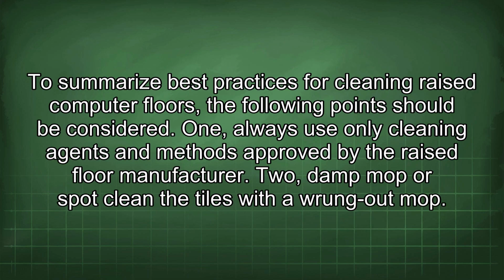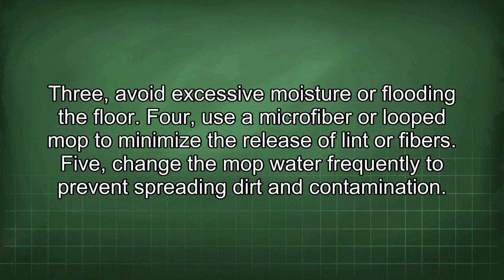To summarize best practices for cleaning raised computer floors, the following points should be considered. 1. Always use only cleaning agents and methods approved by the raised floor manufacturer. 2. Damp mop or spot clean the tiles with a wrung-out mop. 3. Avoid excessive moisture or flooding the floor. 4. Use a microfiber or looped mop to minimize the release of lint or fibers.